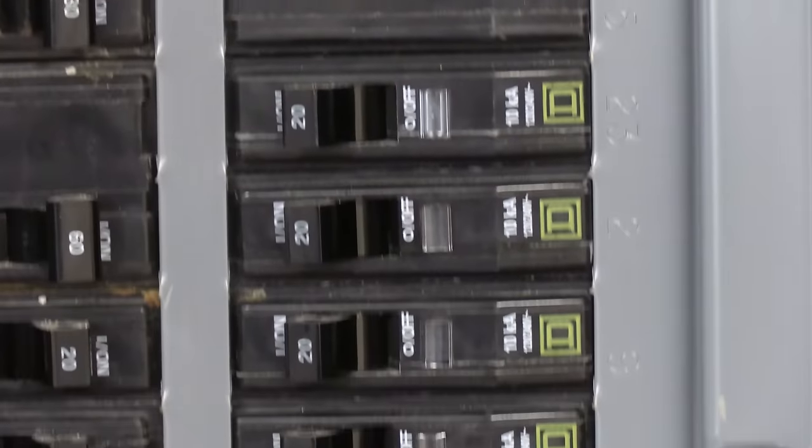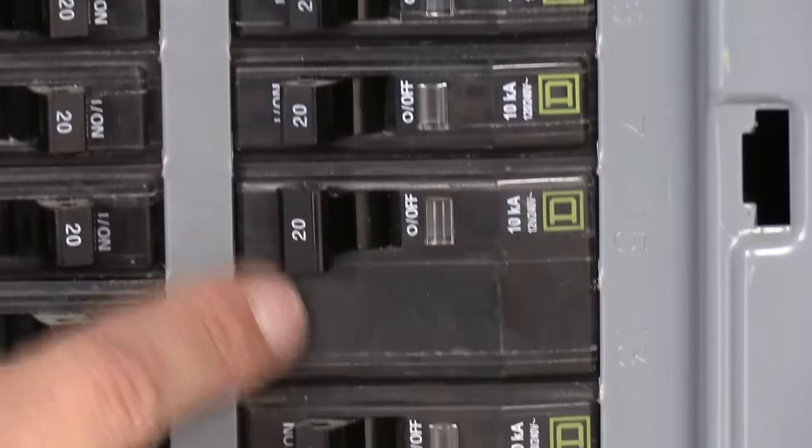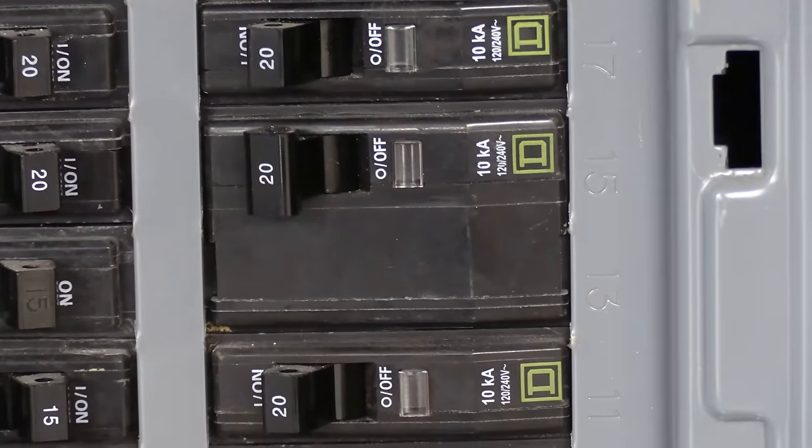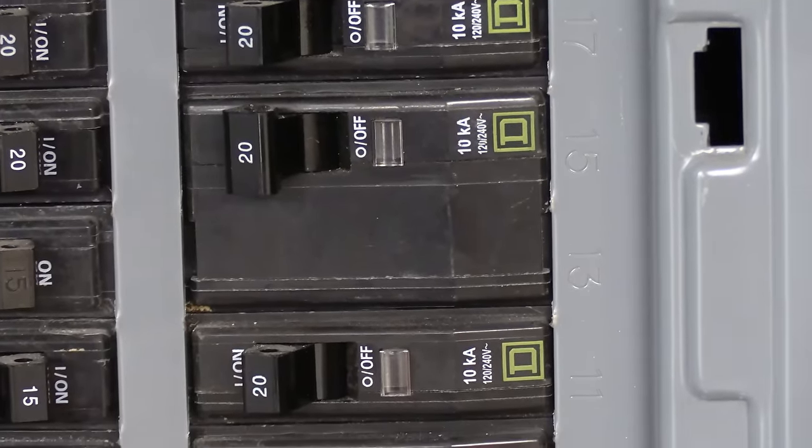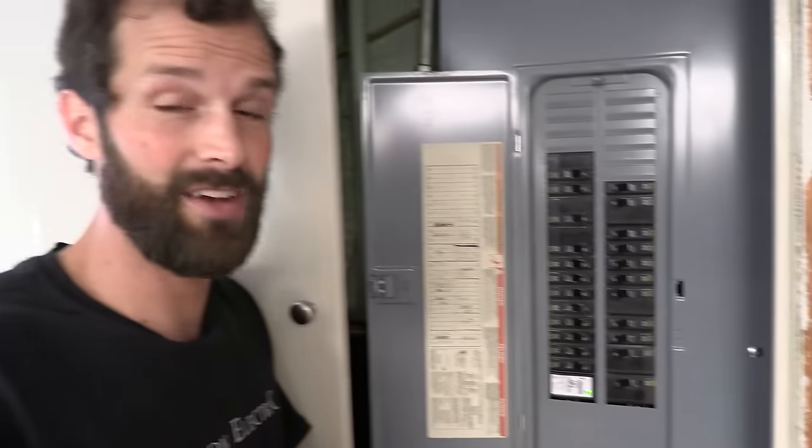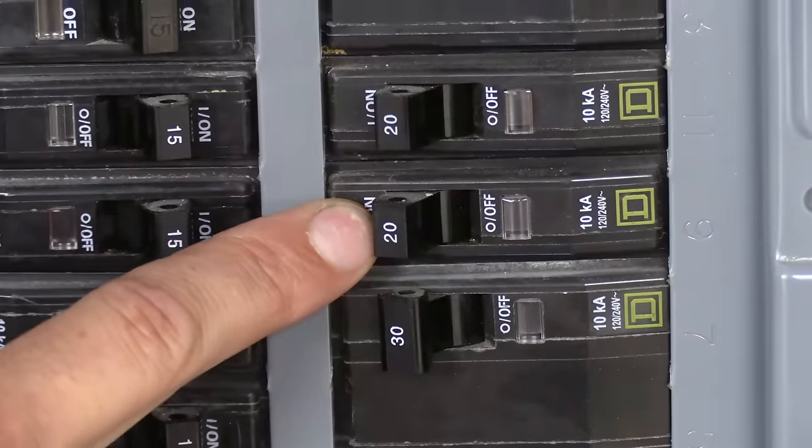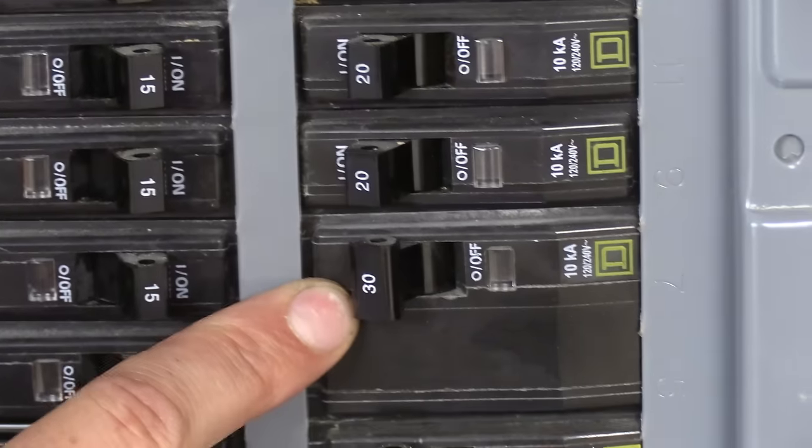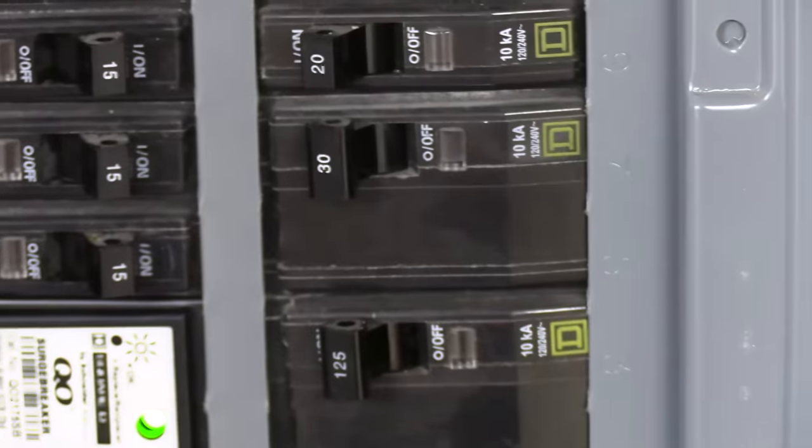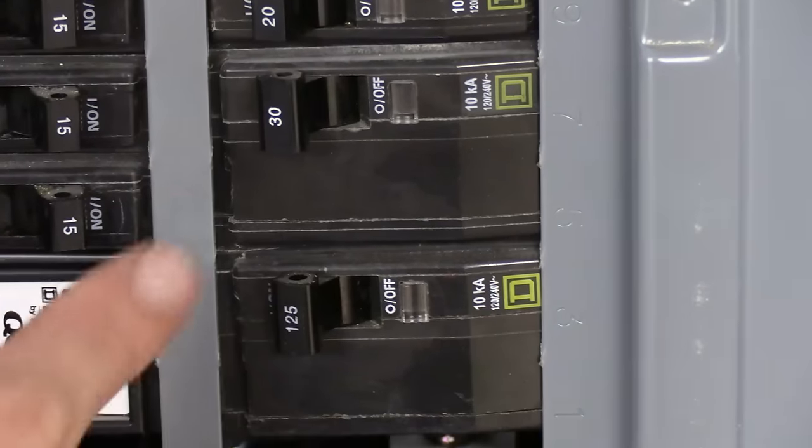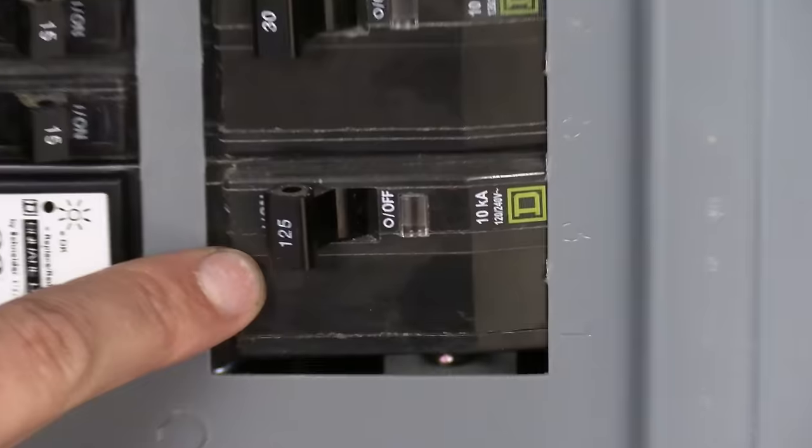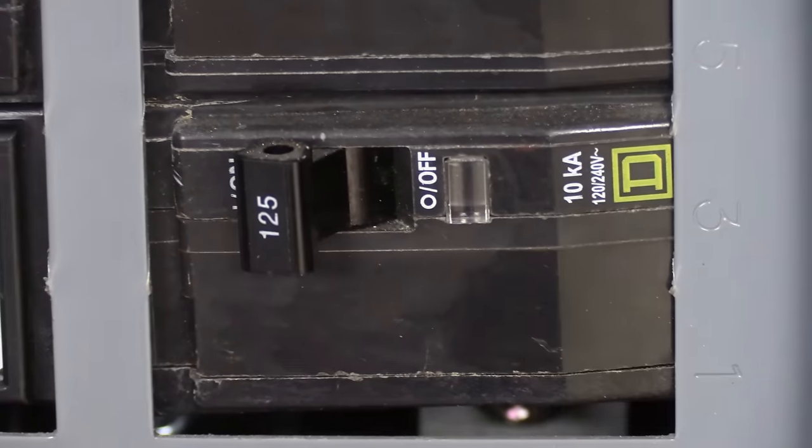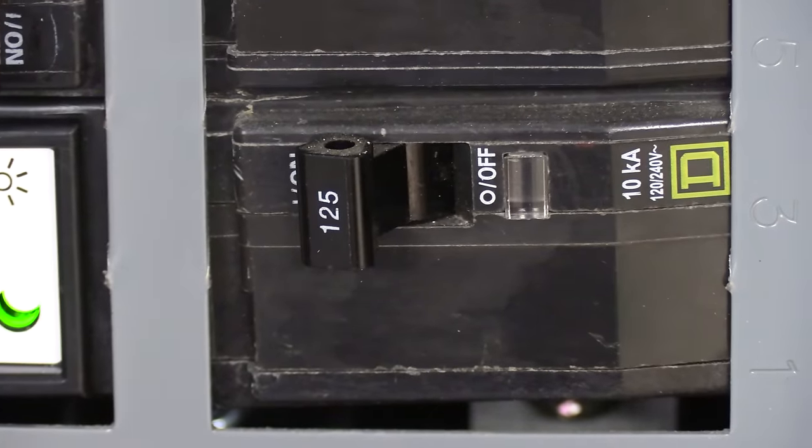I've got multiple 20 amp breakers. This two pole 20 is kind of interesting. That could be an air conditioner, a pool pump. It could just be a multi-wire branch circuit. That's effectively two circuits that are sharing one neutral. Then I've got more 20 amp breakers here. Two pole 30 says H2O. I'm guessing that's water heater. Kind of clever shorthand there, but might be confusing. And this is the main, which is not marked here, but it does say main over here. So this is not a service disconnect because my service is outside on the carriage house and that's the service disconnect. Here, this is just the main, meaning the main shut off for this electrical panel.